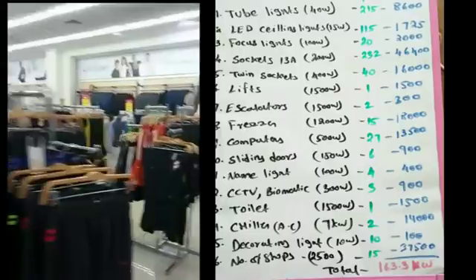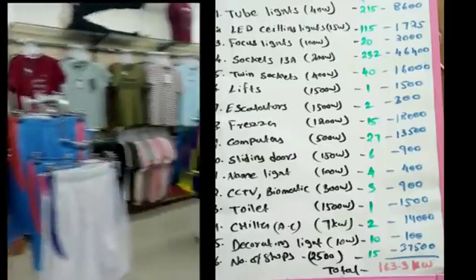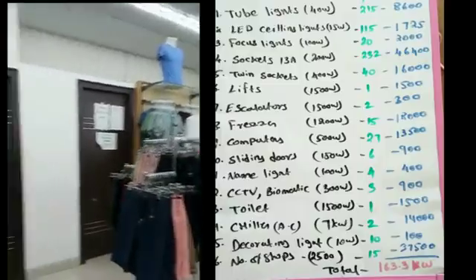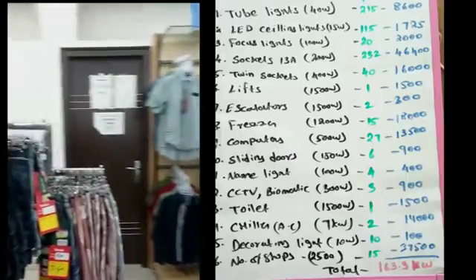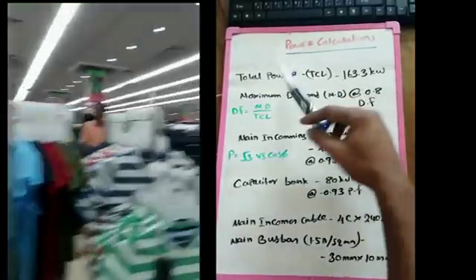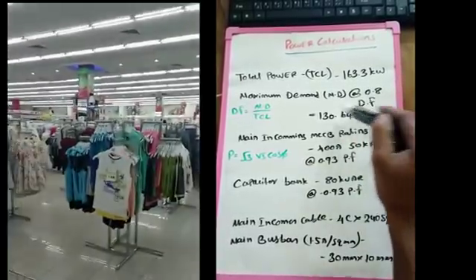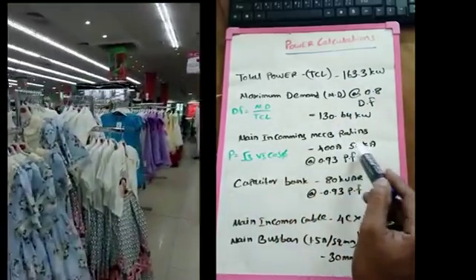There are two chillers - you can see the ground floor and the first floor. Each is 7kW, so this is 14kW total. If you look at all of this, we can see the total power connected is 163.3kW. The maximum demand - with a diversity factor of 0.8 - gives you a maximum demand of 130kW.